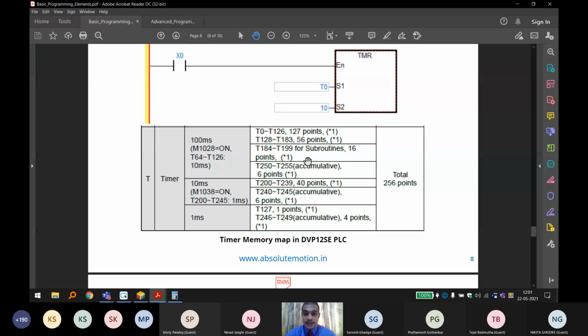These timers can only be implemented in multiples of their time base. For example, if I want a timer of 500 milliseconds, I can implement it by multiplying the 100 millisecond base by 5. But if I want a timer of 550 milliseconds, I can't use this time base since I can't multiply by a non-whole number. I'll have to use the 10 millisecond time base instead.